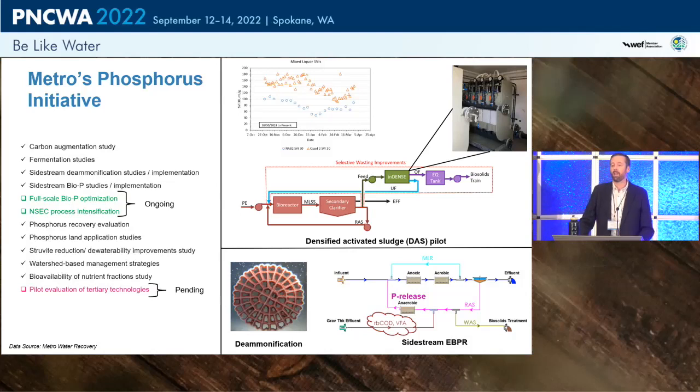The sidestream EBPR configuration uses an anaerobic reactor on RAS, reducing footprint. Since there's no influent carbon available in the sidestream, gravity thickener effluent was used as the food source, which had adequate VFAs and RBCOD to drive P-release. The advantage is a tighter footprint and maximized use of existing basins.